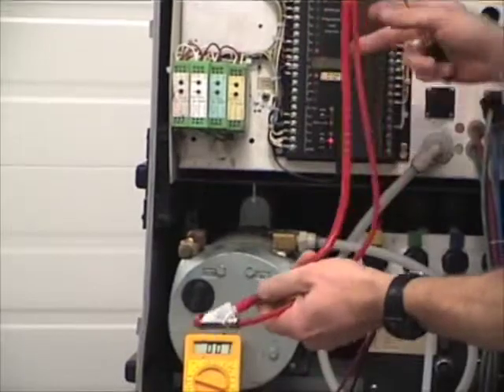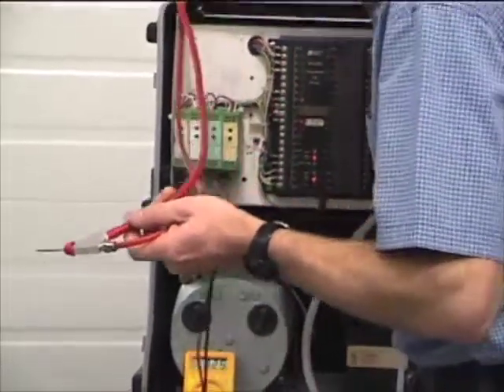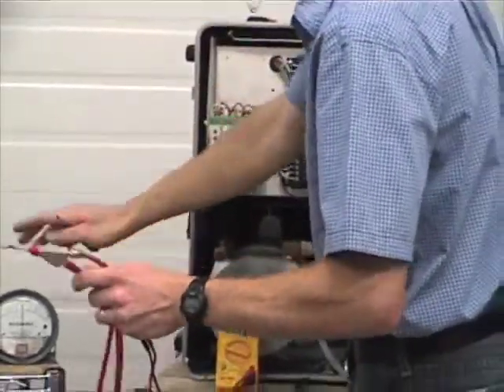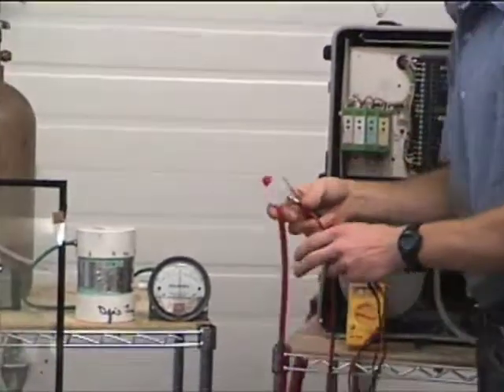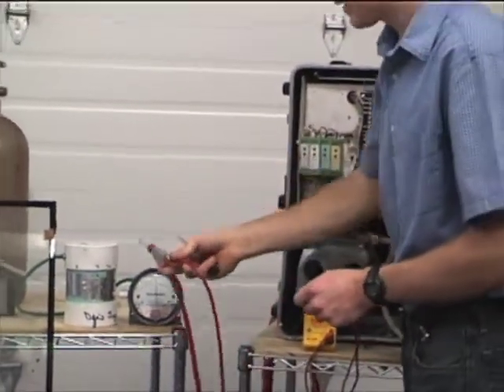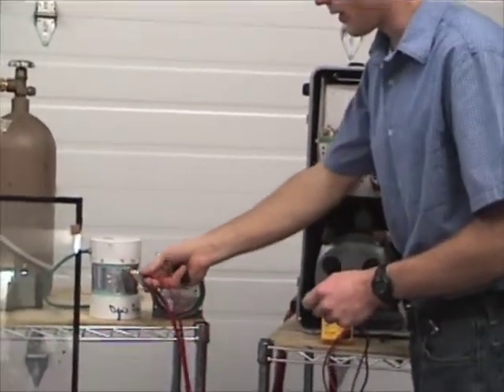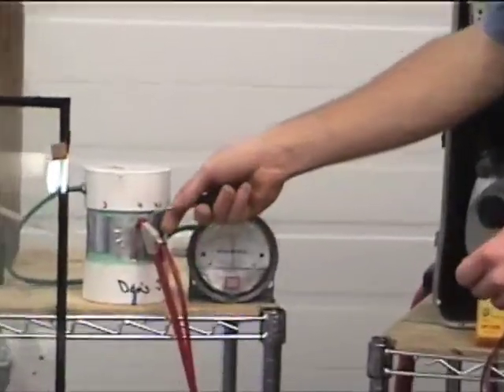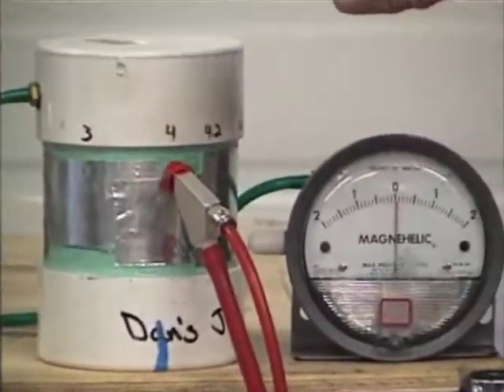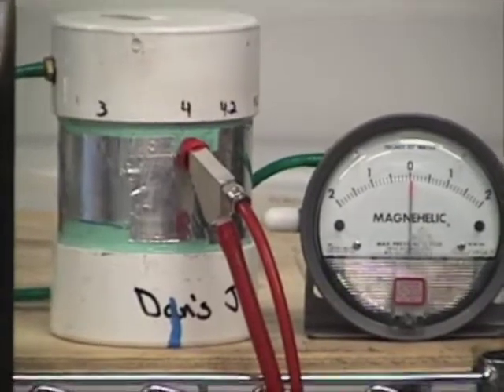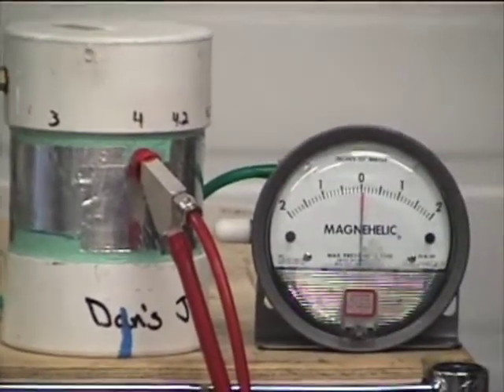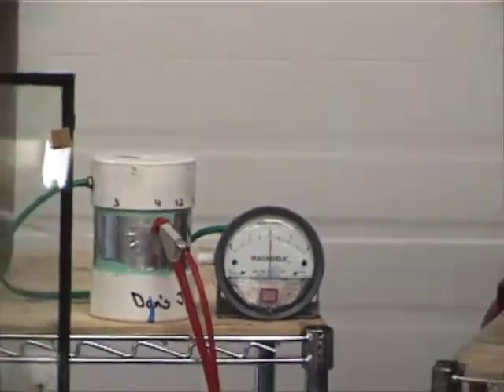Now the second step in the calibration is using the test jug and the magnehelic, and we want to put the lance in a hole that's been drilled in the test jug, and that hole needs to be the same size hole as you're using in your spacer bar. So you're actually replicating a unit with this test jug.